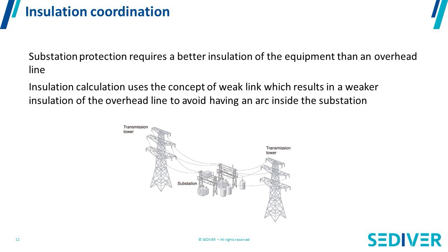Of course, in a substation you also have other protections — surge arresters, circuit breakers, all kinds of equipment to protect it. But the basic first fundamental rule in insulation coordination is that by definition, you design your overhead line as the weak link. So if any arcing activity occurs, it happens on the line and not in the substation.